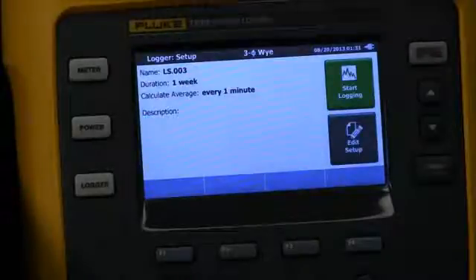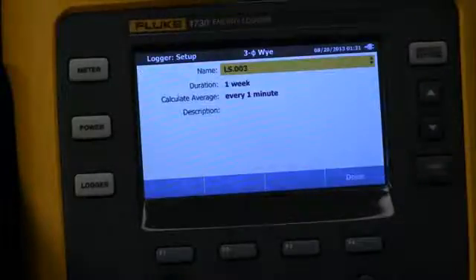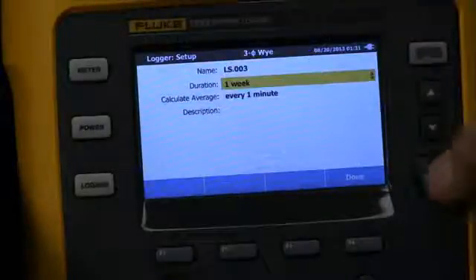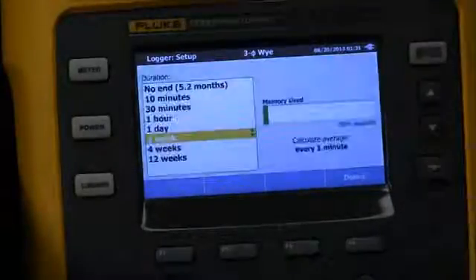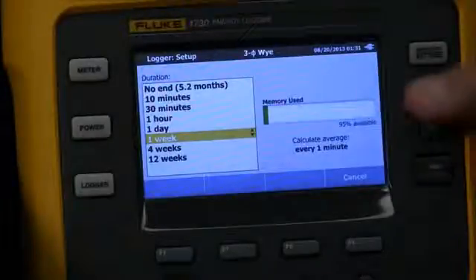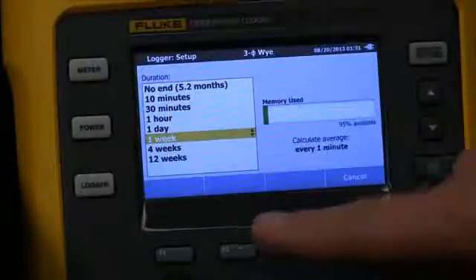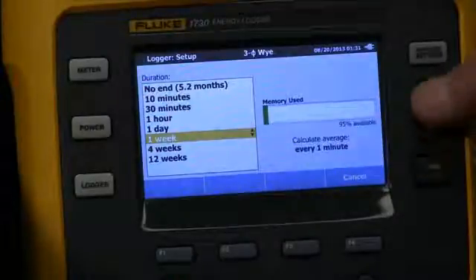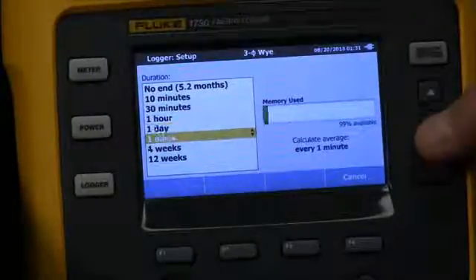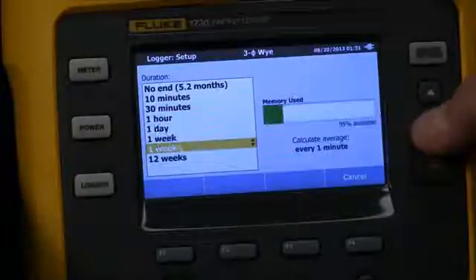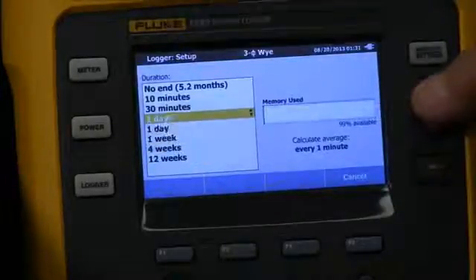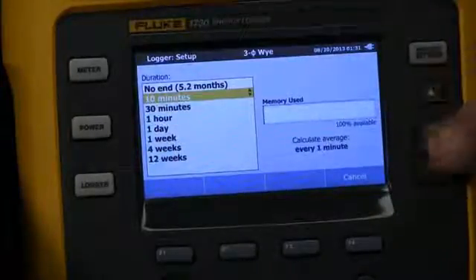When we go into the logging here, let's go ahead and edit the setups. We want to make sure that we've selected the proper duration here. So we scroll down and select enter. Here we select the duration of time. The nice thing about selecting the time is it's also going to show us how much memory is available for that. As we go further and further out, it tells us how much memory will be used for that length of time, whether it's 12 weeks all the way down to 10 minutes for the duration.